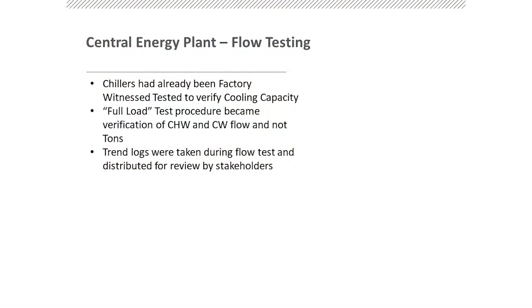In essence, what we thought was, I've got to see six chillers under load. We would see three occasionally, but you want to see six chillers loaded up. But do we need to see six chillers actually loaded in this plant, since they were factory witness tested? You put the chiller on the stand, it gets its design water flows on both sides, and you can see its performance and you have all that data. So do we really need to see that again in the space? We've seen them all operate individually, just not six together. The chillers have seen that, and the cooling towers have seen their load, each of them in the space running with the different chiller connections. So what do we really need to test for full load? Because that's what we kept calling it, the full load test. And it was the water.